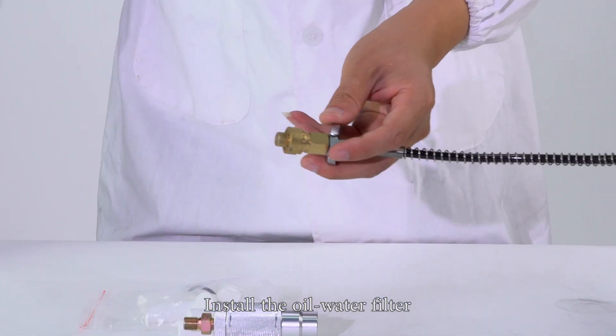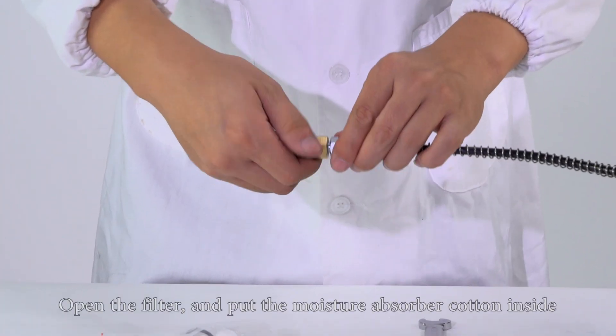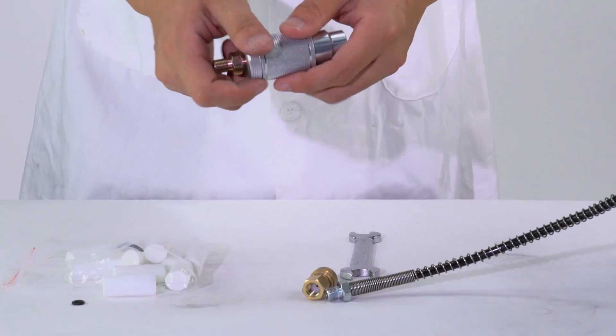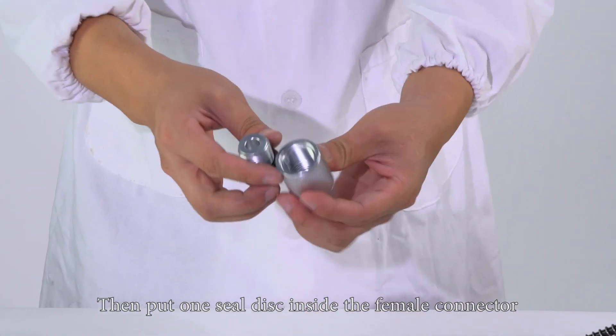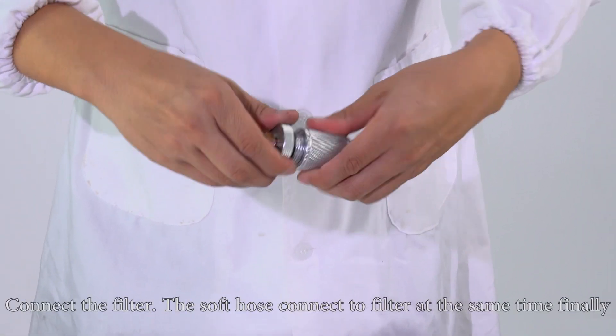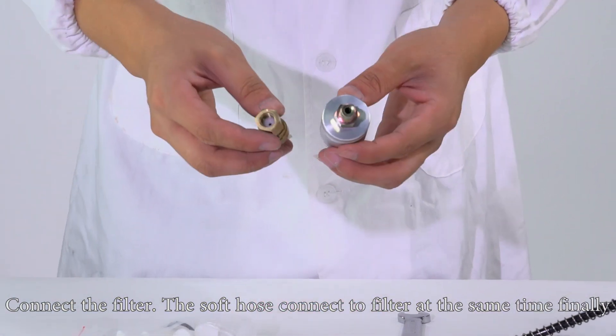Install the oil water filter. Disconnect the soft hose and female connector. Open the filter and put the moisture absorber cotton inside, then put one seal disc inside the female connector. Connect the filter. The soft hose connects to the filter at the same time finally.